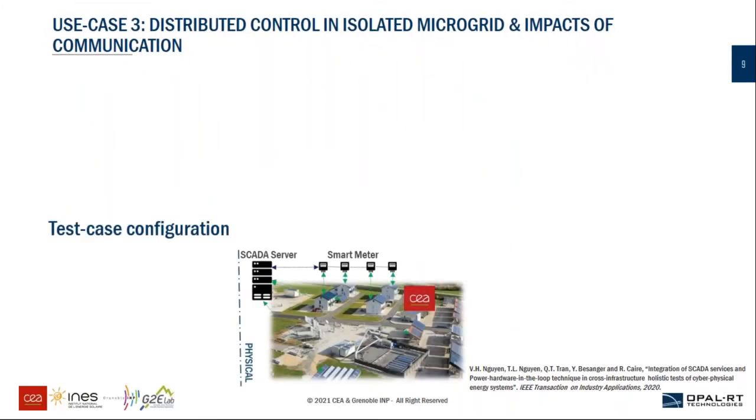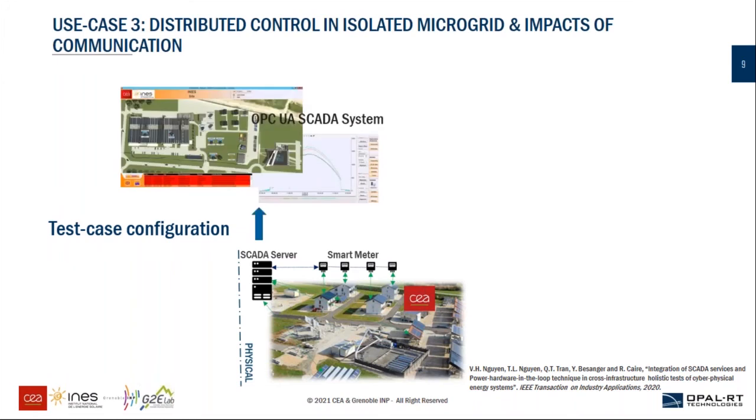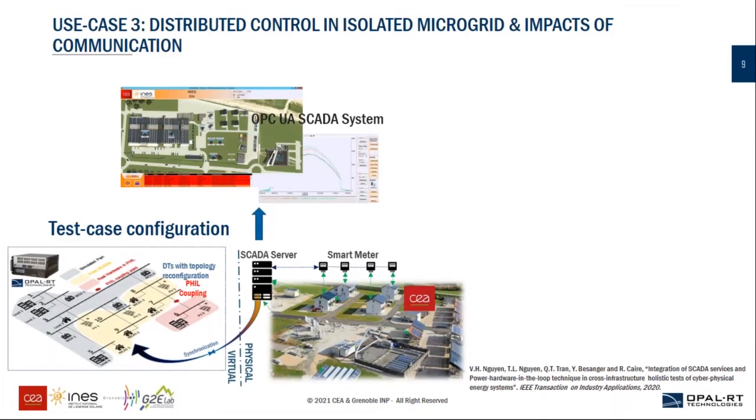So the power path of the microgrid is located in the PRISM platform of CEA-INES in Chambéry, France. And in this case study, we would like to integrate the digital twin of a real PV and load linked with the SCADA system of CEA INES to get the measurements in real time and to inject them into the microgrid simulated in the real-time simulator in OPAL-RT. The smart house and the PV park, with 20 and 60 silicon monocrystalline panels, and a PV inverter are physical hardware and are synchronized to the test via the OPC-UA SCADA system.